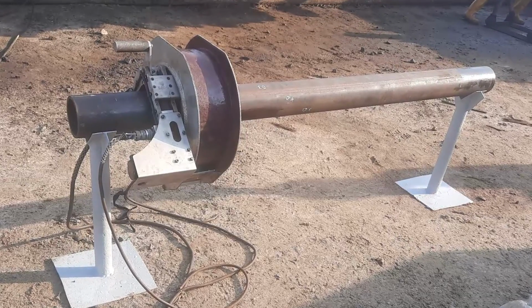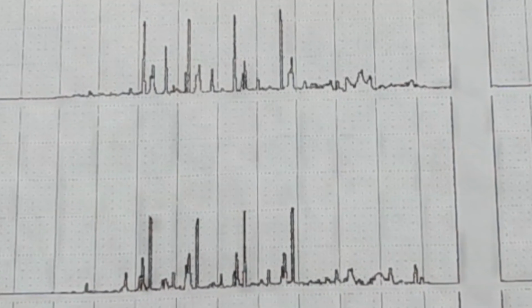That means there are a total of 8 shoes. We have to calibrate all 8 shoes. The calibration standard pipe has 8 full penetrated holes. Each hole has a 1/16 inch diameter plus or minus 1/64 tolerance. And the pattern of the full penetrated holes is a spiral pattern. So we have to calibrate. Each shoe sees a 1/16 inch diameter hole, and an equal amount of flux will leak from that hole or from that material discontinuity. We have to adjust each shoe so that the graph has the same kick. All the kicks should be the same height. That is the calibration.